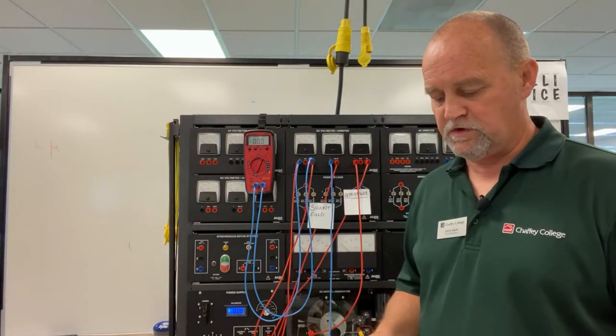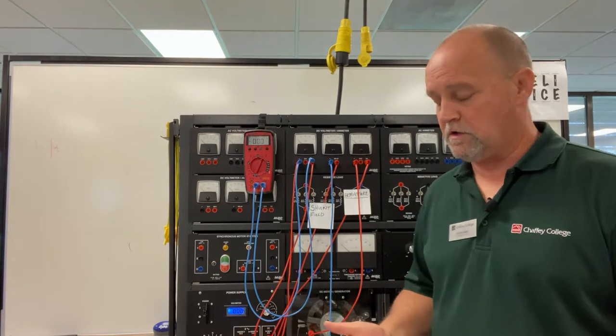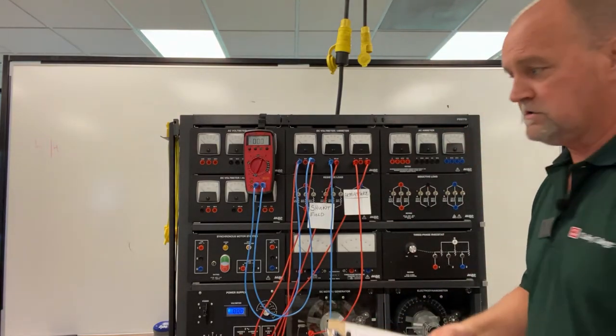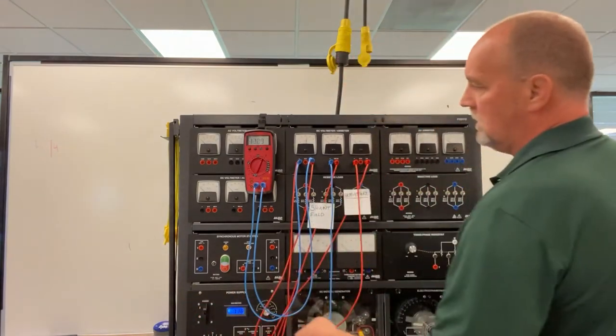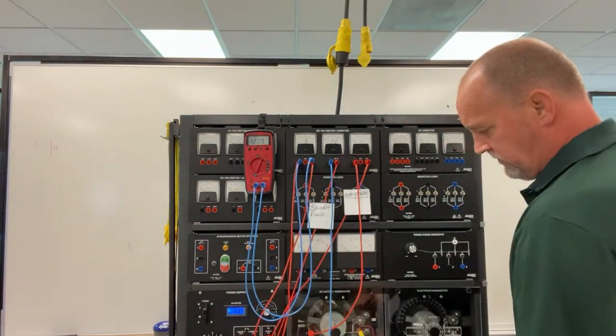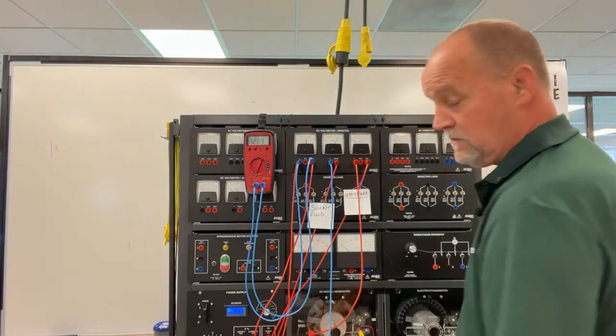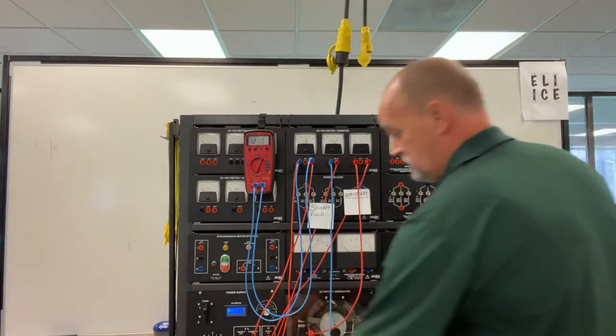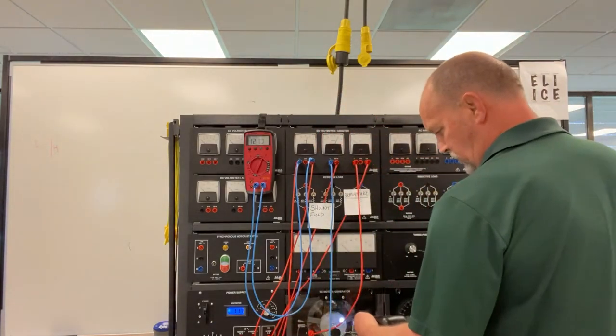And so, on this first reading, they want us to do it with no load. So, we've got the belt taken off. And we just need to make sure that we're seeing 120 volts on our meter. And we are. I've got the shunt field set to 400 milliamps. And really, it just wants an RPM reading off of the motor with no load.